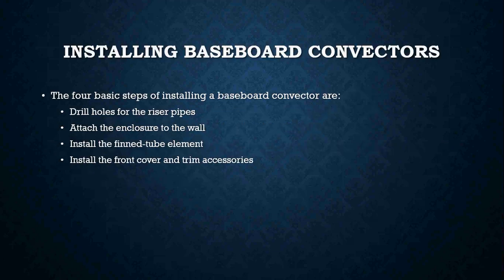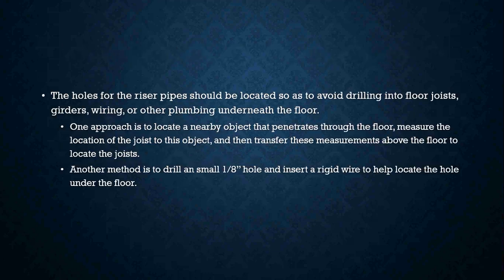When installing baseboard, there are four basic steps: first, drill holes for the riser pipes that go through the floor; then attach the enclosure to the walls; then install the fin-tube elements; and then put the front cover and trims on. The holes for the riser pipe should be located to avoid drilling into floor joists, girders, wiring, or other plumbing underneath the floor. Before drilling, go downstairs to the basement to make sure you have a clear path and won't be cutting wires or drilling through a water line.